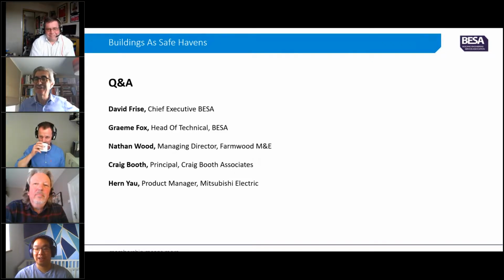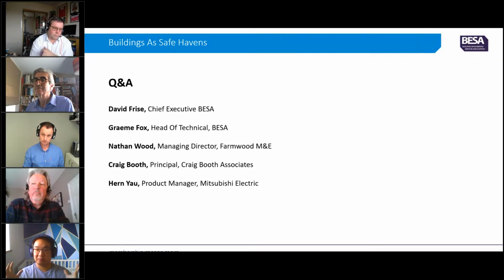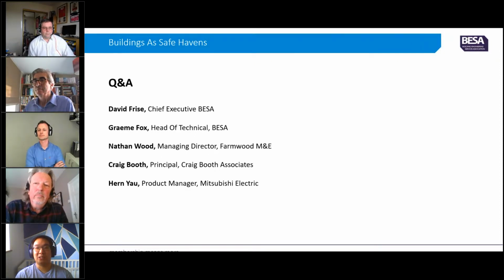No, I completely agree. Just increasing the fan speed when something's been designed at a lower rate might be okay for a short period of time, in the pandemic world we live in at the moment, where it's all taken us by surprise. But the consultation part is trying to make sure we design that into buildings as a foolproof thing, and there needs to be consideration into the noise and the comfort in those scenarios. I think first and foremost, the movement of the air is the most important thing we need to achieve, but we need to make sure we're not doing it in such a way that occupants go, I'm not interested, it just isn't practical. So that's something we need to take into account.